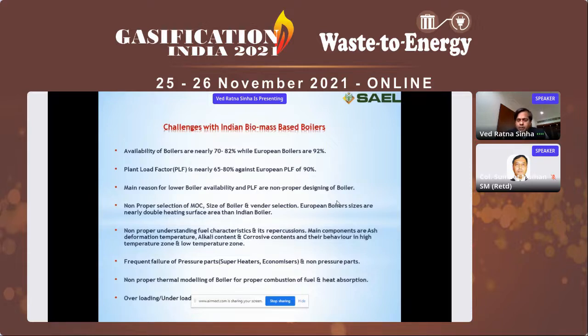There is often non-proper understanding of fuel characteristics and their repercussions — main components being ash deformation temperature, alkali content, corrosive contents, and their behavior in high and low temperature zones. If biomass is not properly analyzed for these typical parameters, it creates problems in plant operation and availability, along with cost inflation. This results in failure of pressure parts, especially superheaters, economizers, water walls, and other pressure parts, as well as improper thermodynamic design of the boiler for proper combustion and heat absorption.